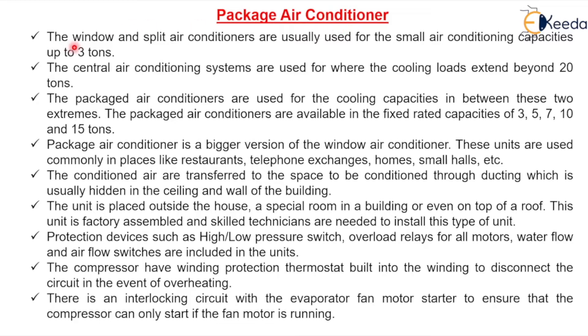Packaged air conditioner. Window AC and split AC are usually used for small air conditioning capacity up to 3 tons. Central air conditioning systems are used where the cooling load extends beyond 20 tons. The packaged air conditioning systems are used for cooling capacity in between these two — that means 3 to 20 TR.